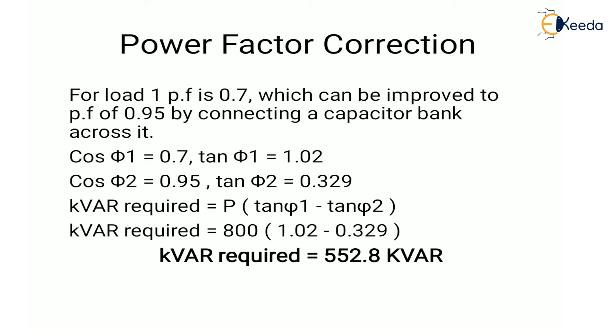Once we have found the KVA rating, next we find the power factor correction. For load 1, the power factor is 0.7, which can be improved to 0.95 by connecting a capacitor bank across it. So cos φ1 = 0.7 (lowest) and cos φ2 = 0.95 (highest). Using the formula KVAR = P × (tan φ1 − tan φ2), the required KVAR value is 552.8 KVAR.